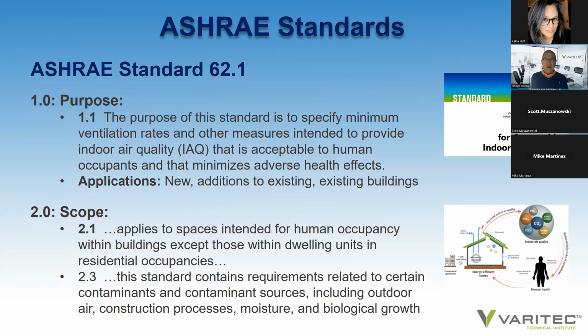It actually defines the minimum ventilation rates. ASHRAE's epidemic task force stated that in order to reduce the risk of infection, buildings need to make sure that they are receiving the minimum outside air prescribed by 62.1 to create a healthier environment. This task force also recommends increasing your outside air to even further reduce the risk of infection.